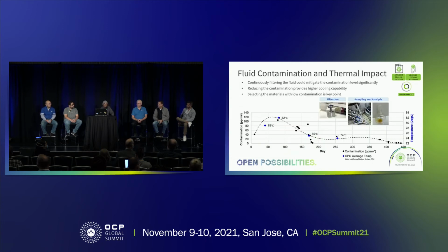All right. And here are some actual data from the project, which I find fascinating. We take the fluid periodically and we analyze it by gas chromatography, and we can calculate the total hydrocarbon concentration, quantified here in parts per million. You'll see the junction temperatures on the processors follow the contamination level pretty closely. At points where the concentrations were high, you could see oil on the boiling surfaces in some cases, and the junction temperatures are impacted by that.